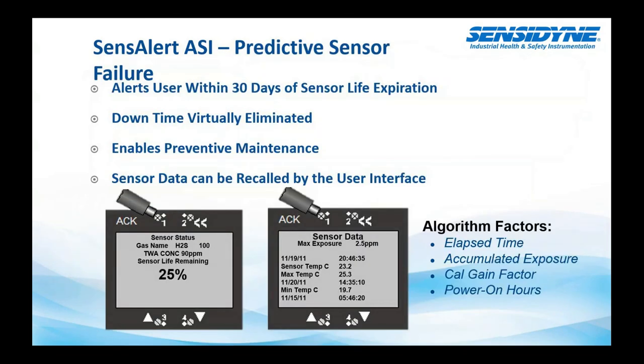As I discussed earlier, we also have this predictive sensor failure. What this does is allow the user to define within 30 days of the sensor life expiration. And actually you can set it to less than that if you wanted to, but 30 days is a good rule of thumb. It eliminates downtime and enables preventative maintenance. So this is an algorithm that looks at the elapsed time the sensor has been on, the accumulated exposure to the target gas, the gain adjustment or gain factors, which are changed every time you do a calibration, and the power on hours.